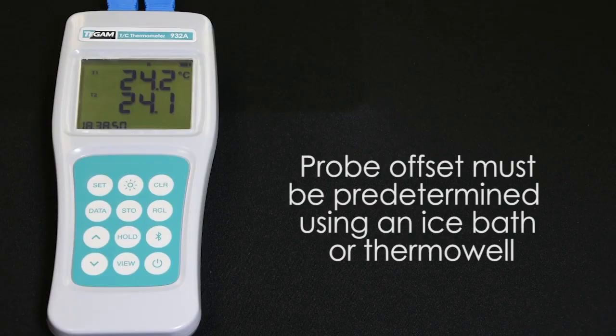Probe errors are the largest contributor to overall temperature measurement uncertainty. The probe offset feature of the TEGAM 900 series thermocouple thermometers helps minimize those probe inaccuracies. In order to use this feature, the probe offset must have been determined previously either through the use of an ice bath or a thermowell.